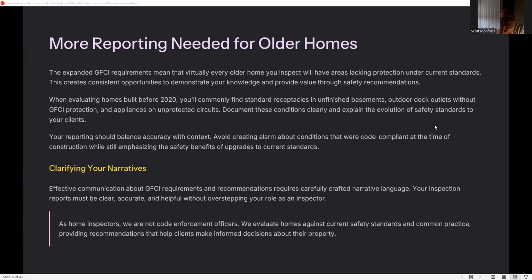More reporting needed for older homes. The expanded GFCI requirements mean that virtually every older home you inspect will have areas lacking protection under current standards. This creates consistent opportunities to demonstrate your knowledge and provide value through safety recommendations. When evaluating homes built before 2020, you'll commonly find standard receptacles in unfinished basements, outdoor deck outlets, and appliances on unprotected circuits. Document these conditions clearly and explain the evolution of safety standards to your clients. Your reporting should be balanced and accurate, with context. Avoid creating alarm about conditions that were code compliant at the time of construction.